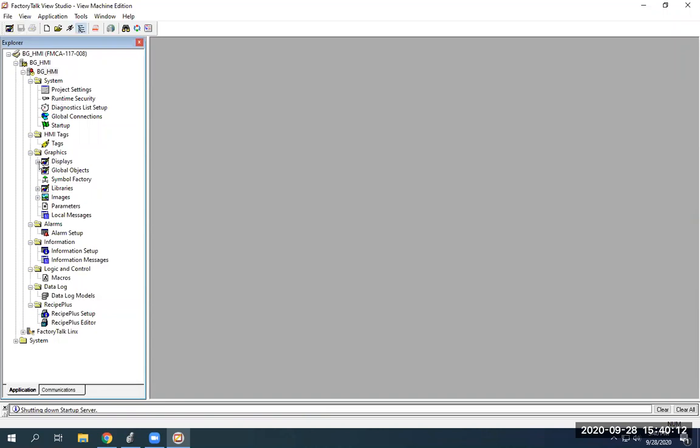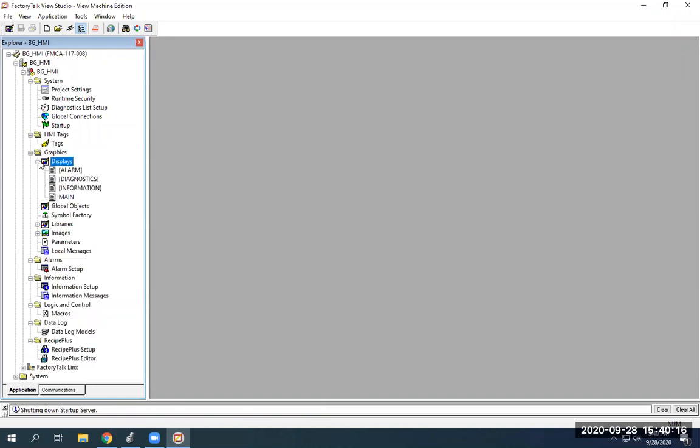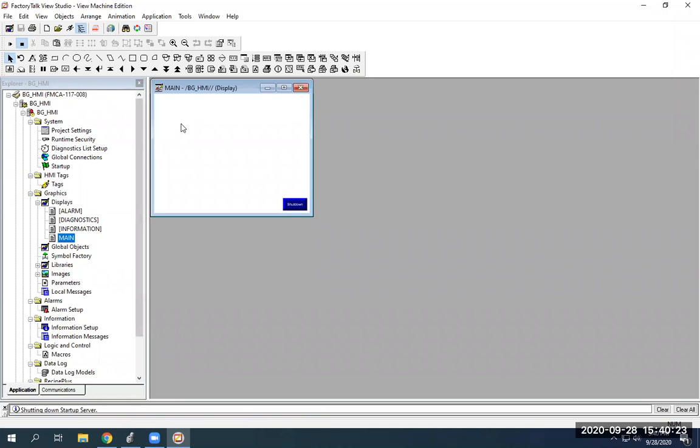You can add a display or you can use the main that we have here. If you expand the display, you'll see alarm diagnostics, information, and main. I'm going to double-click on main — this is our main display within the HMI program. You can have a main display and click on buttons to take you to other screens. Your main is just your default that it opens to. What I'm going to do is add in a couple of momentary push buttons. You have momentary and maintained — maintained means if you push it, it doesn't go off until you push it again.